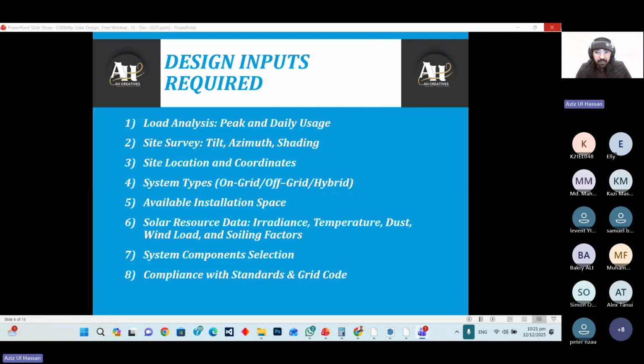Okay, the selection is very important: the PV module, the inverter, the MV stations, and other things. And also the grid compliance with the standards and the grid codes. For a large scale project, like 100 megawatt or 200 megawatt, when we are connecting our solar system to the grid of that existing company, like TANESCO in Tanzania or ESKOM in South Africa, we have to follow their standards. What is the kVAR requirement of that grid? What is the requirement of the active power of that grid? What is the minimum and maximum variation in the voltage? What is the variation in the power factor? We have to comply with those standards.